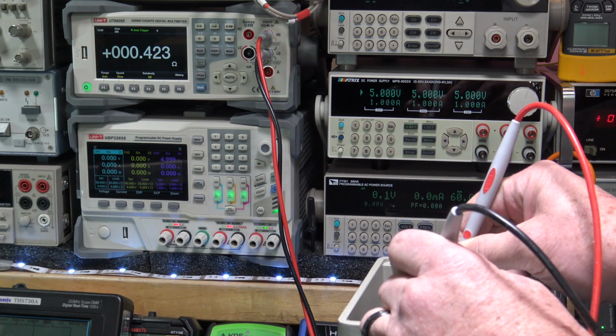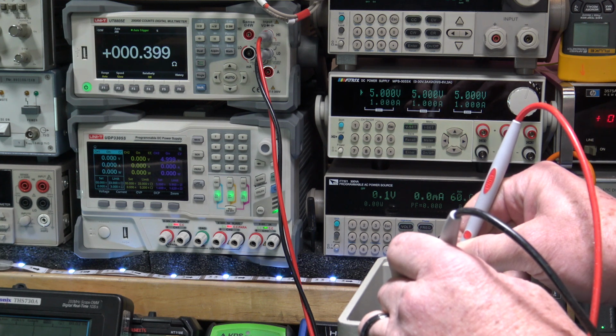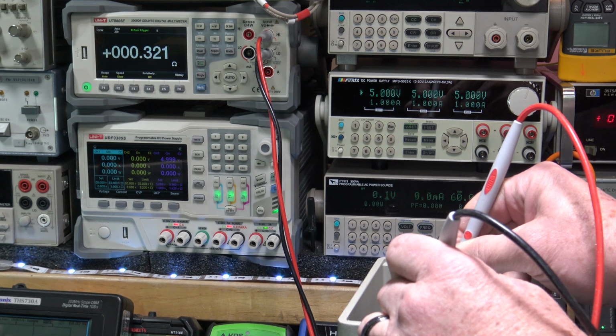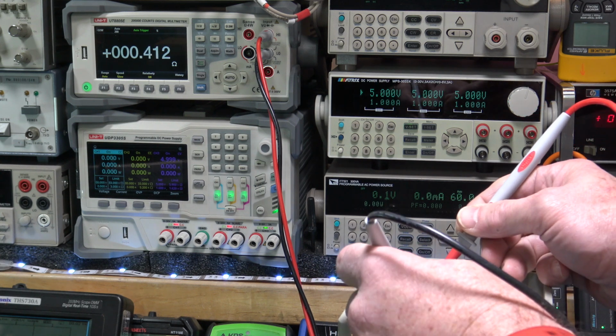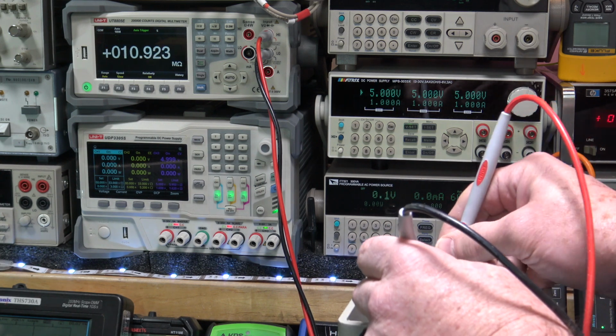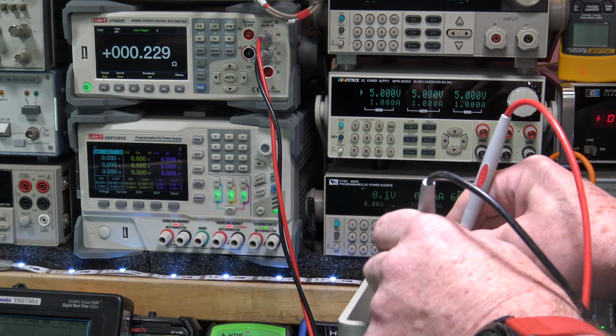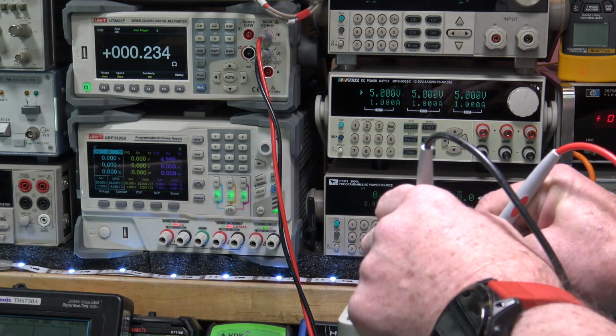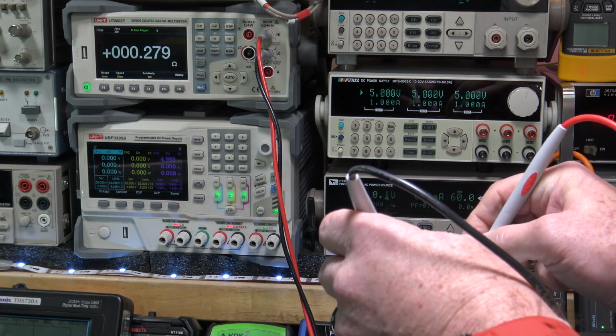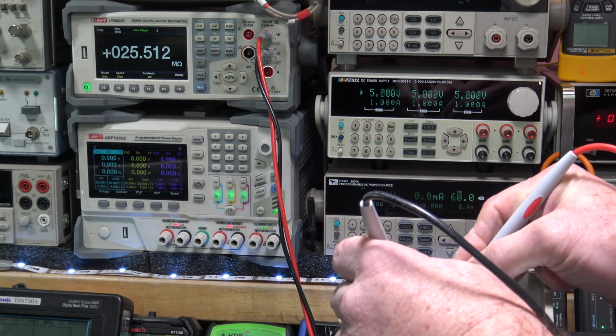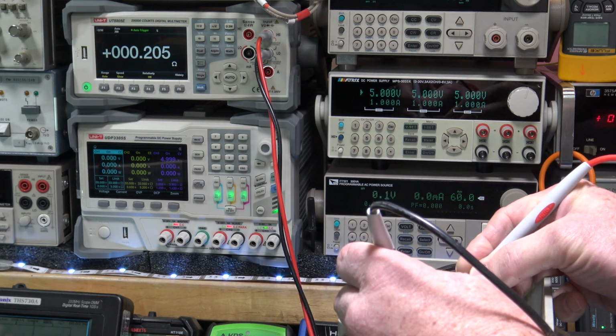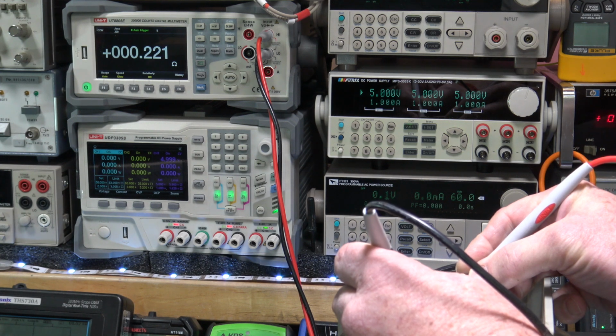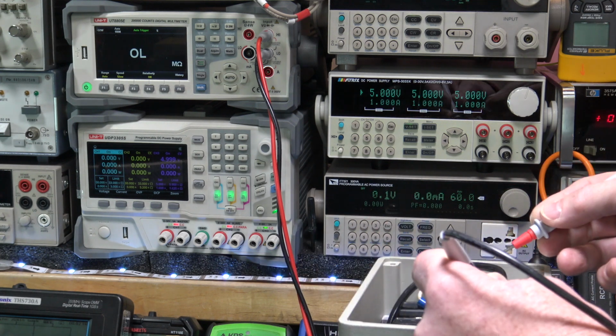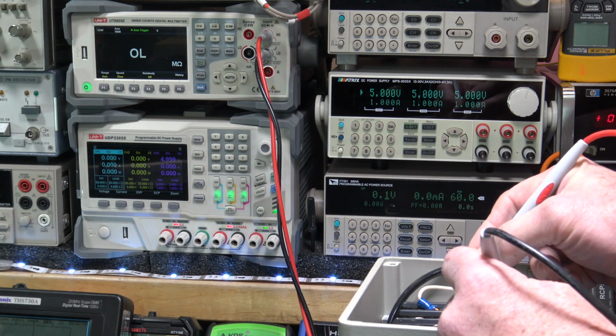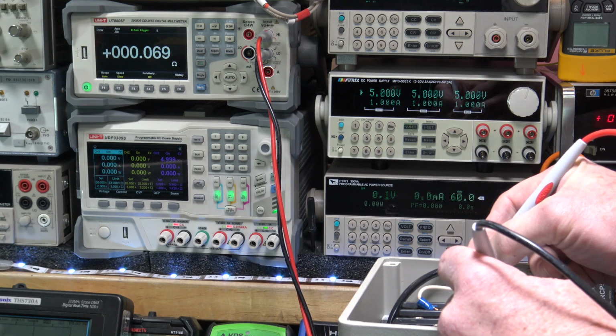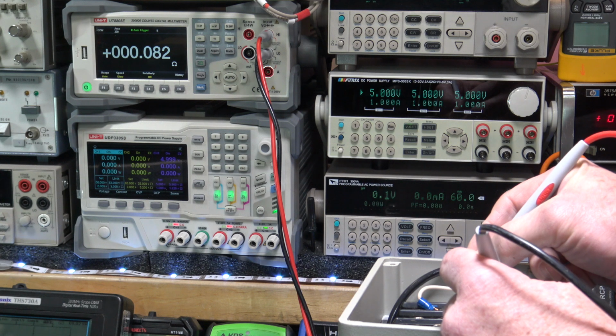But that is pretty low ohms for a big old transformer. And also the fact it's jumping around. That's weird. Okay, I'm going to go to the other windings, H3, H4, that we're not using. Okay, it's kind of the same then. That jump around might be me. Okay, I'm going to go back to the other one. H1, H2. Yeah, that jump around is probably me. Okay, so then obviously the screen is tied to chassis. That's pretty low ohms, 0.06.